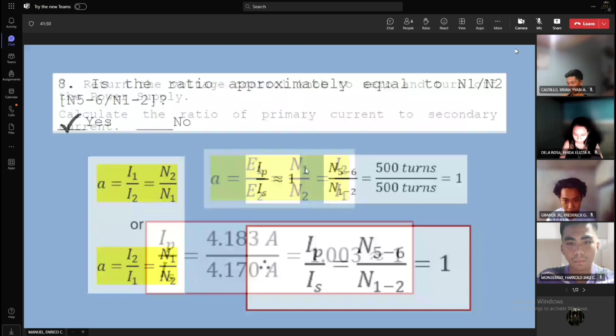Now let us determine if the obtained current ratio is approximately equal to the turns ratio between the primary and the secondary, or in this case, the number of turns between terminals 5 and 6 over the number of turns between terminals 1 and 2. The number of turns between terminals 5 and 6 and between terminals 1 and 2 are actually obtained from our previous experiment, so these are both 500 turns.